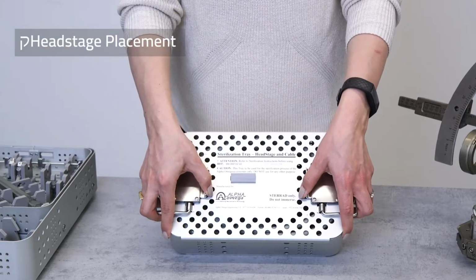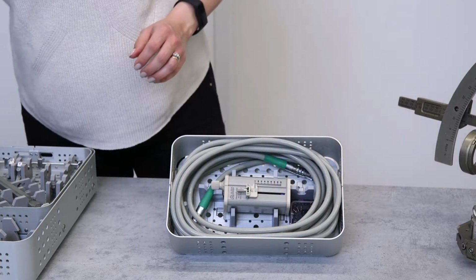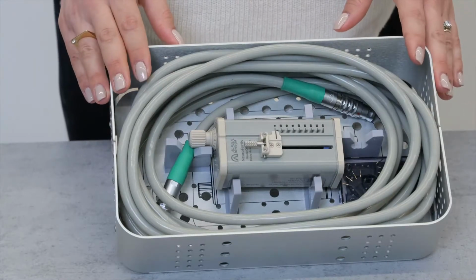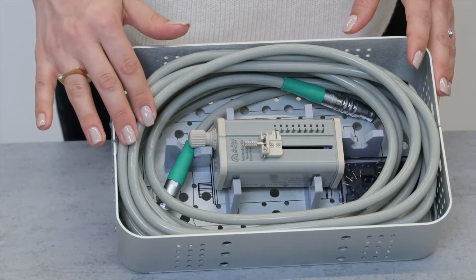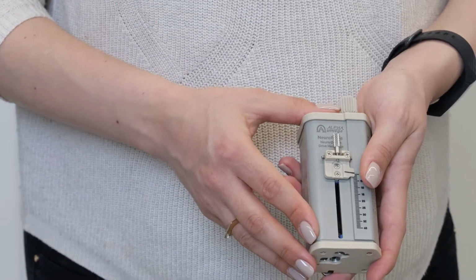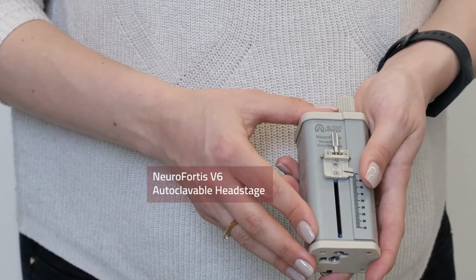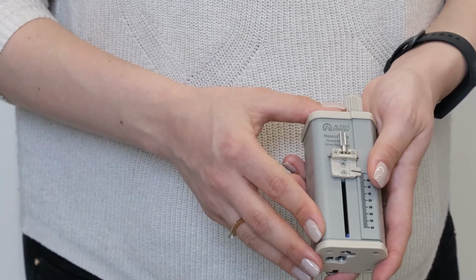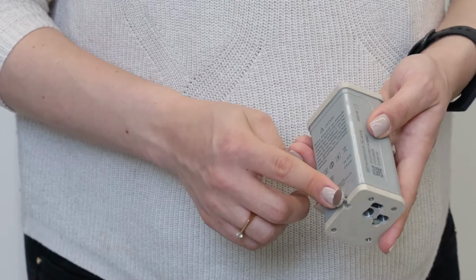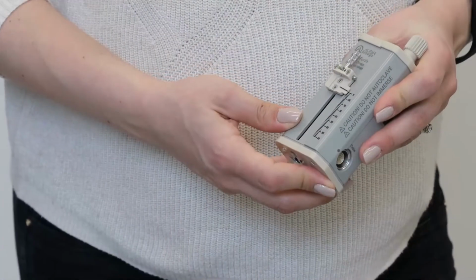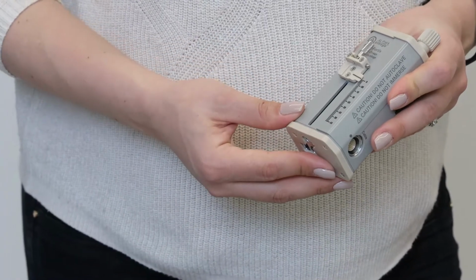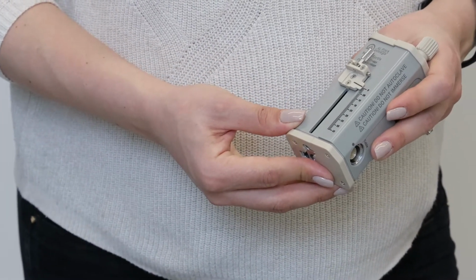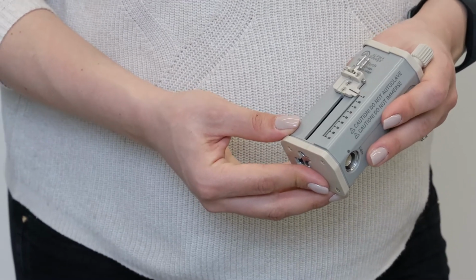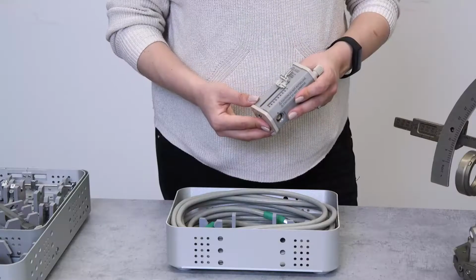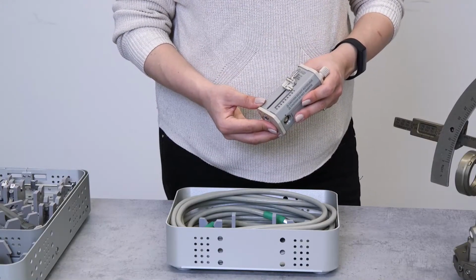Open the Headstage tray. In the tray, we have Headstage, Headstage cable, and ground cable. This is Alpha Omega's motorized washable Headstage, called the NeuroFortis V6 Headstage. Make sure that the screw on the back of the Headstage is there and isn't blocking the holes. The target is always 25 when using Alpha Omega setup with a frame-based or robot. Depending on how far you want to start from the target, you set your starting depth. I want to start 10 above target, so I will set my starting point at 15.